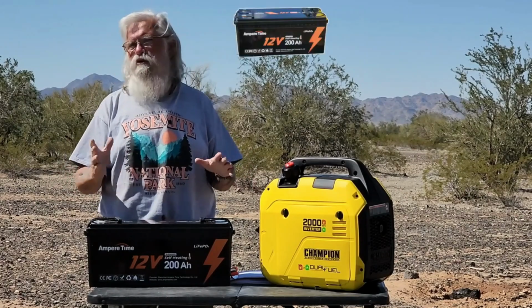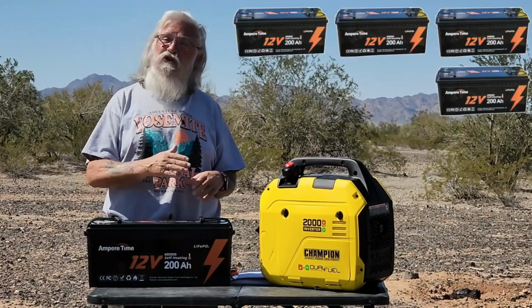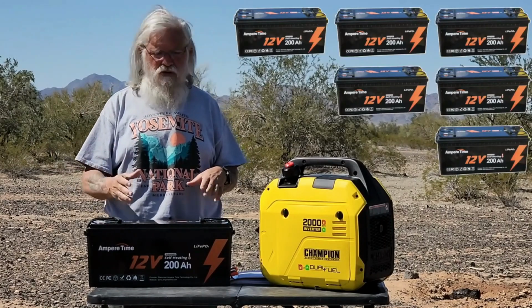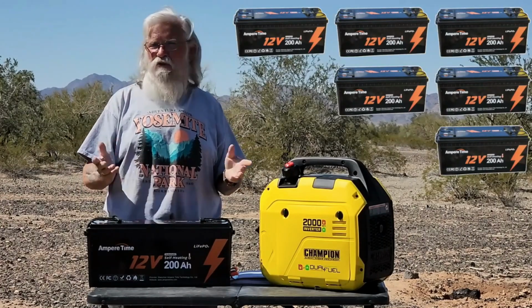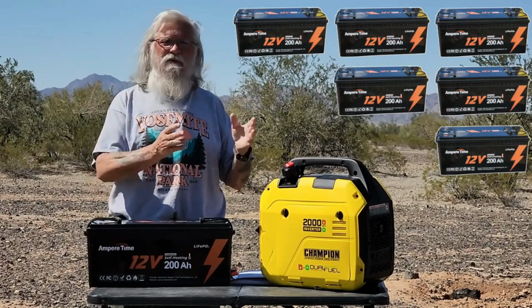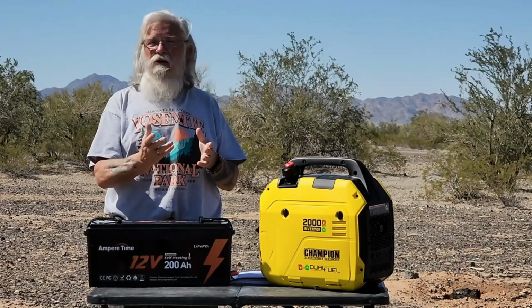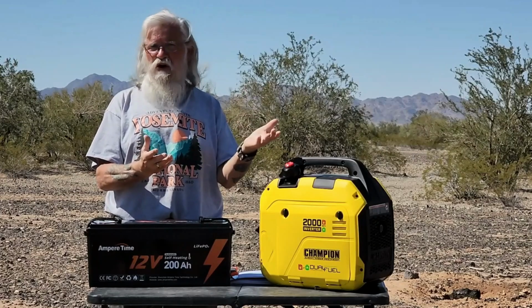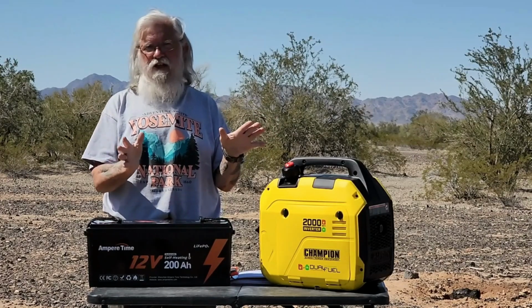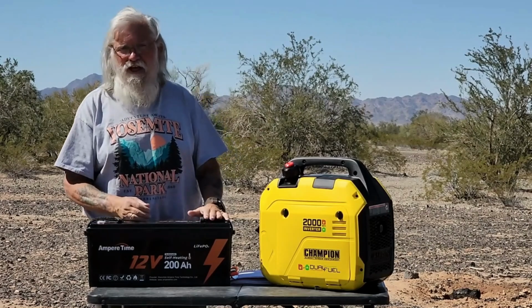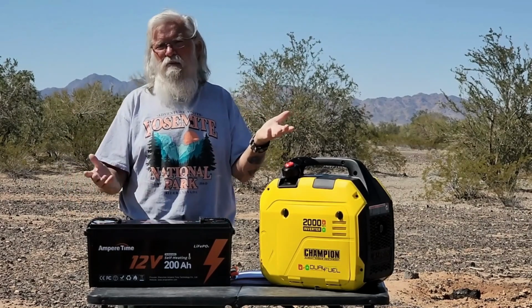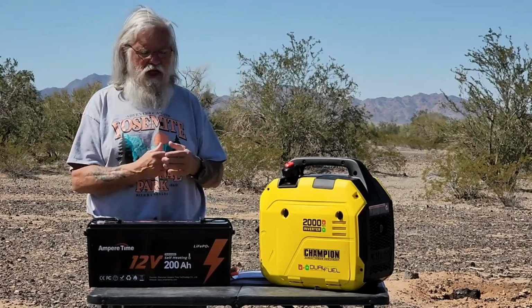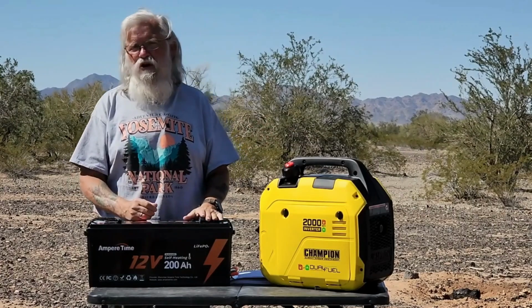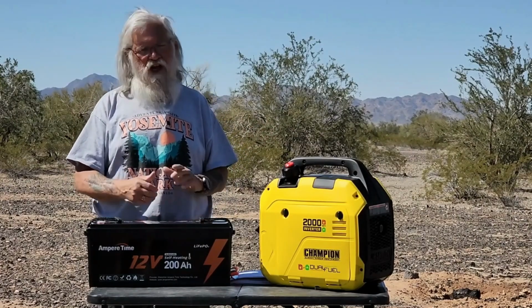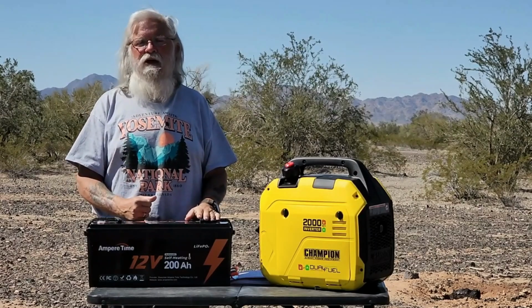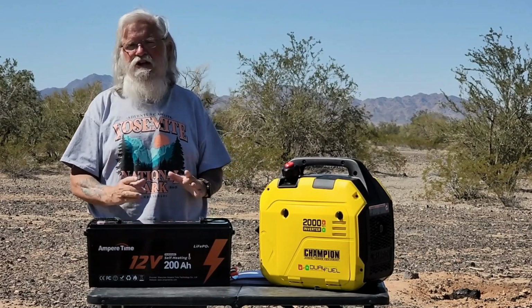That means you can expand your battery bank at any time with no cost or loss in battery capacity. If you have AGMs, an old one and a new one, the new one will never be more full than the old one, and that's a huge disadvantage. The big advantage with lithium is that you can have an old one, say a year old with some use, and a new one, and it will still get fully charged to 100%, because the BMS makes sure this individual battery does it.